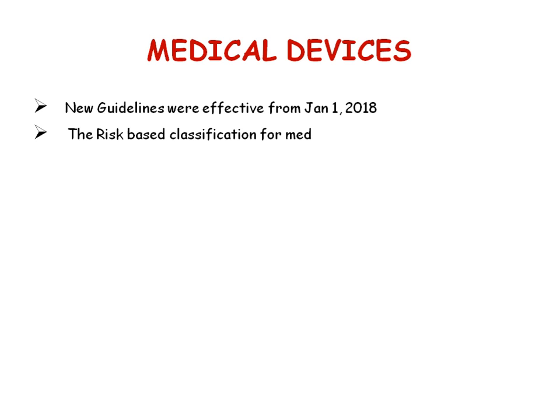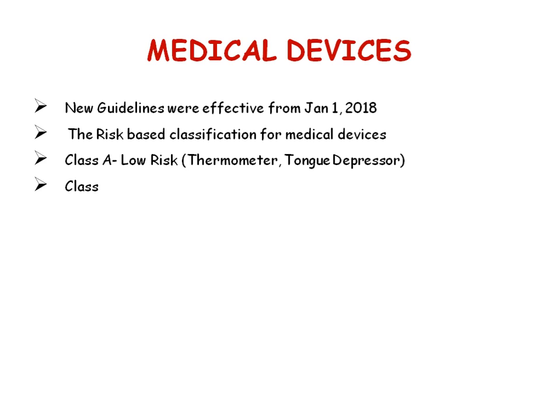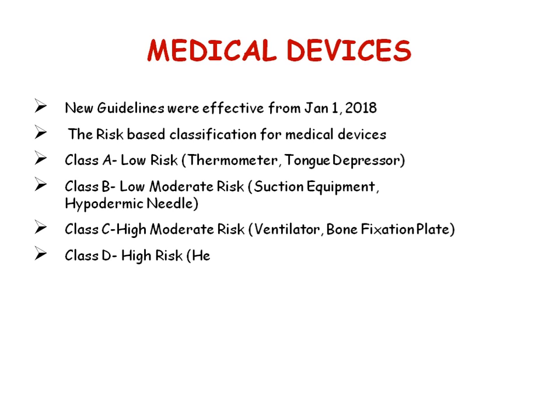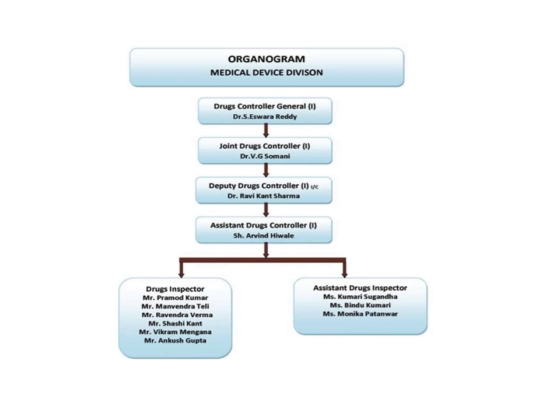For medical devices, new guidelines were effective from 1st January 2018. Risk-based classification of medical devices includes four classes: Class A — low risk devices like thermometers and tongue depressors; Class B — low to moderate risk devices like suction equipment and hypodermic needles; Class C — high moderate risk devices like ventilators and bone fixation plates used in orthopedic surgery; and Class D — high risk devices like heart valves.